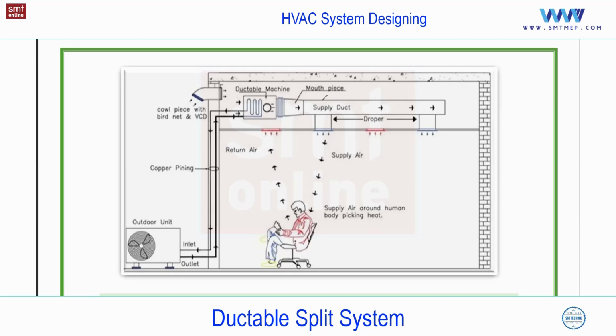In a split high wall or in a freestanding or even in cassette, we can provide, but again, if you talk about split, you will not get the proper option for the fresh air. But in the case of this ducted split, since this unit is placed above the false ceiling as a concealed unit, we can use the duct to provide the fresh air at the suction of this unit as per the standard, as per the requirement based on the calculation.